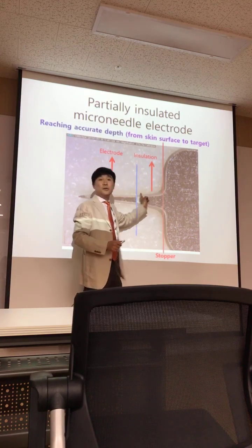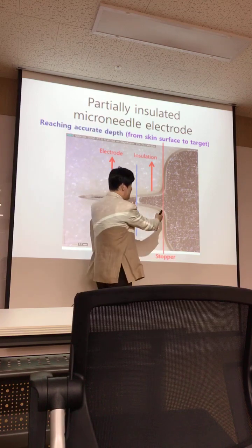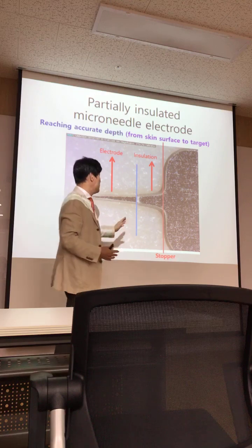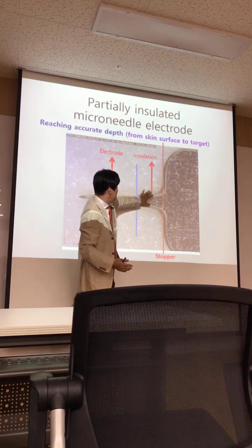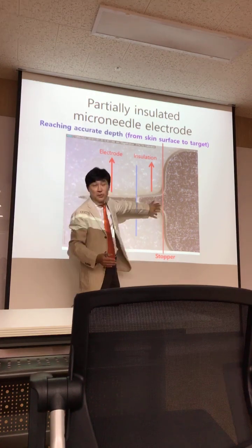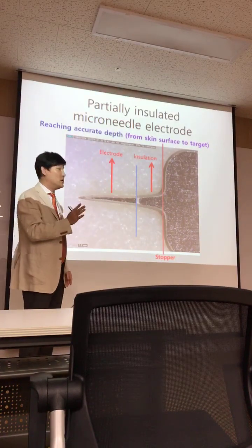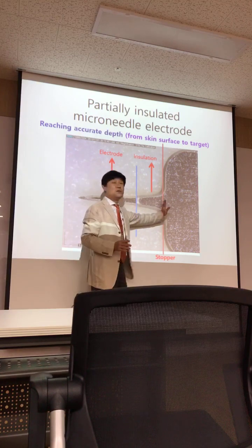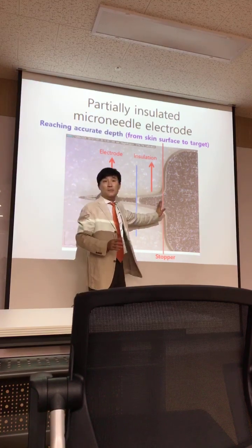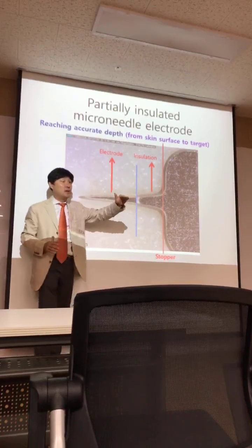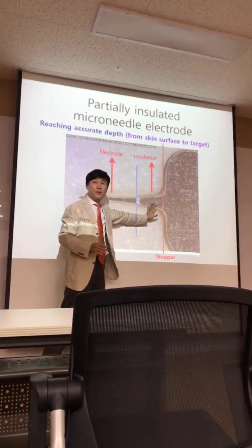And you can see a little bit transparent gelatin-like material. This is the insulation coating. So this insulation protects the tissue from the heat. This length of insulation is very important. For example, in case of acne treatment, we should make 400 micrometer of insulation to protect the skin surface from the sebaceous gland. This is the shortest insulation in the world.